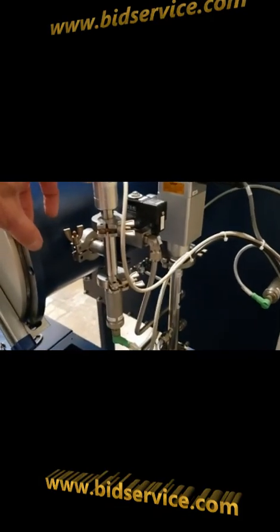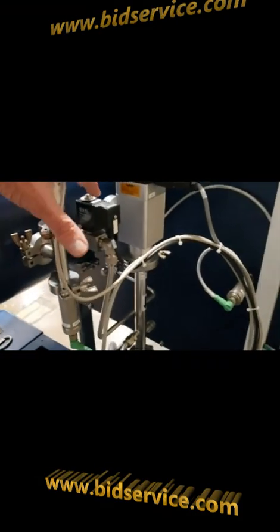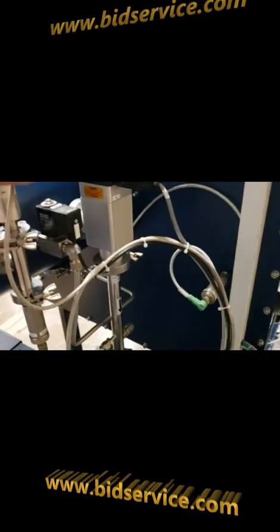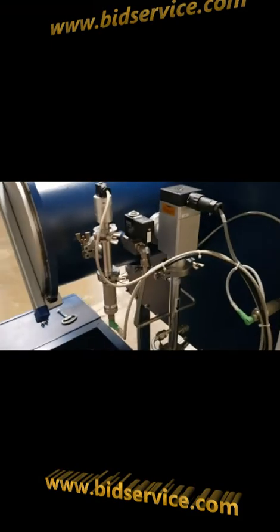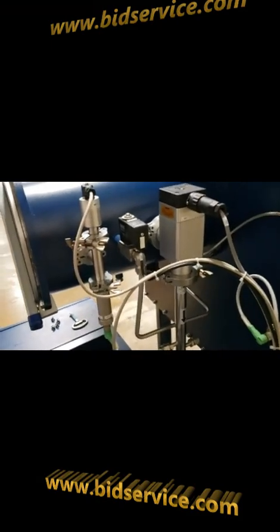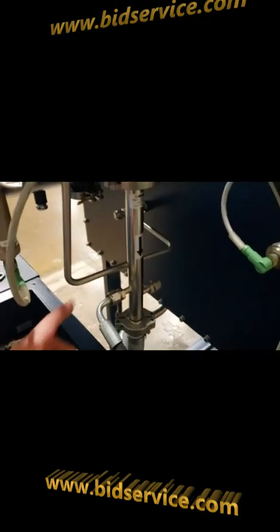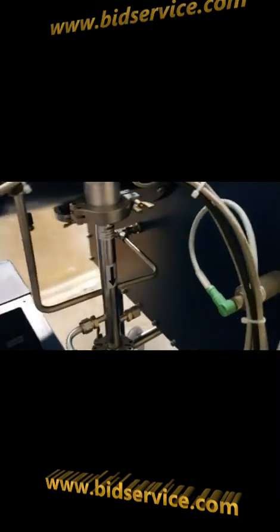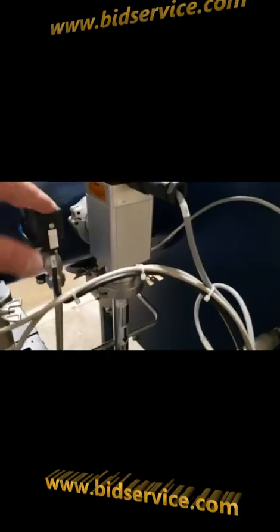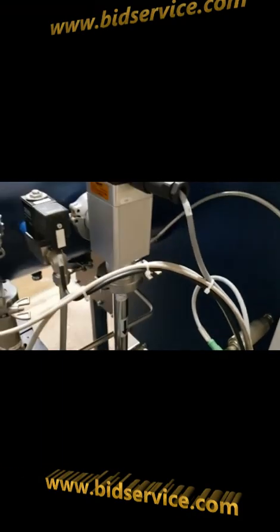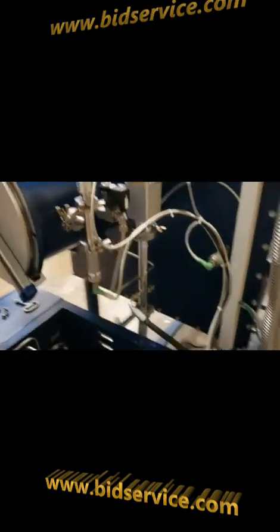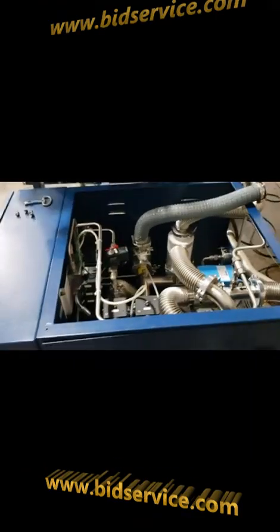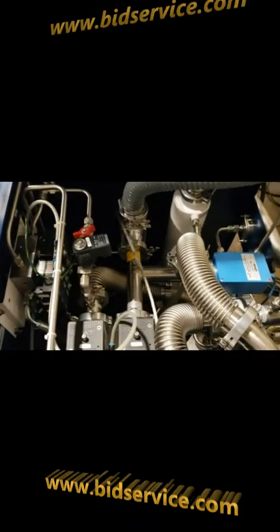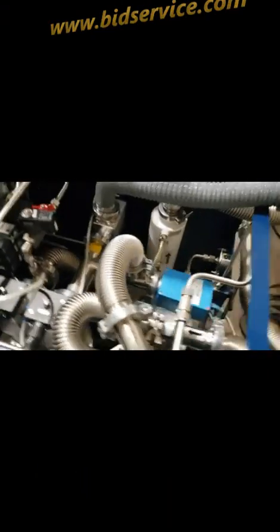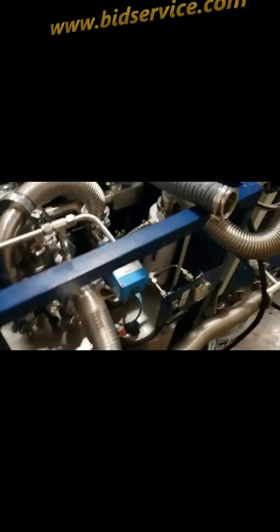And it has a vacuum sensor, atmosphere sensor, refill valve, and evacuation valve. There's a line here that leads to the glove box, the stainless steel line. So as you refill the antechamber, you'll be using the gas from inside the glove box. I have the covers off, just so I can show you the drivetrain here. I got the top cover and the back cover is removed right now. And I'll go on the side.